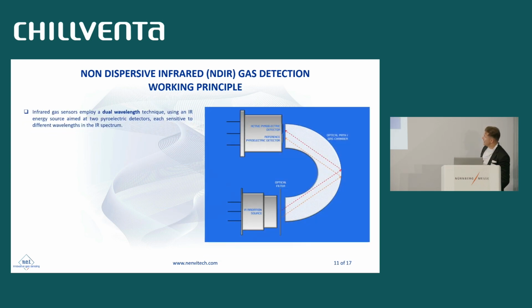Second important property derives from how we build an infrared sensor based on the absorption property we've just seen. How is an infrared sensor made? Well, it's simple. We have an infrared radiation source. It can be a simple filament bulb lamp for typical hydrocarbons, gases, or CO2, or it can be a more sophisticated source like the one we use for our infrared sensors. We have an optical path, which is a so-called gas chamber. This is the space traveled by the light and occupied by the gas in case of a leak.